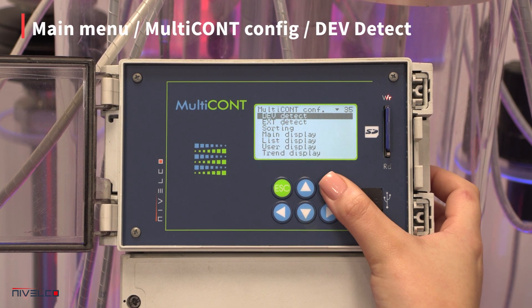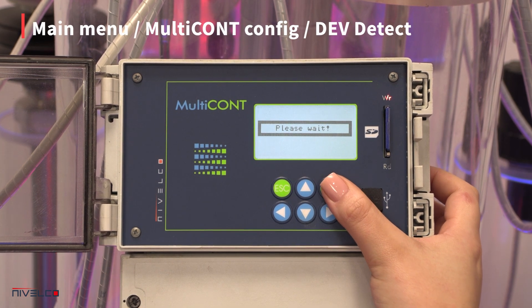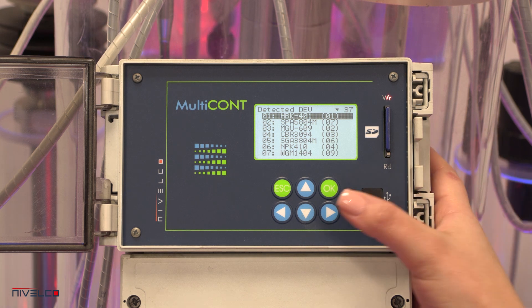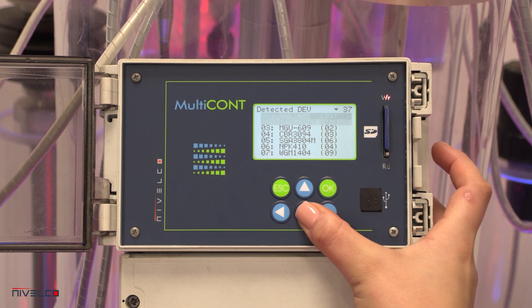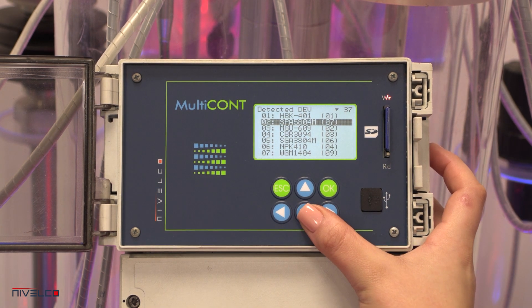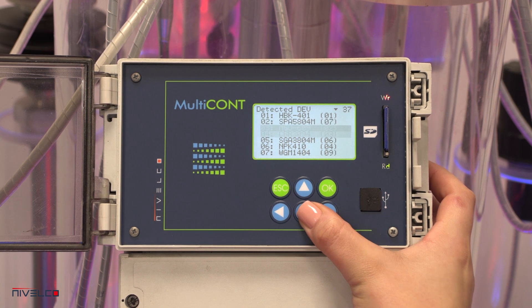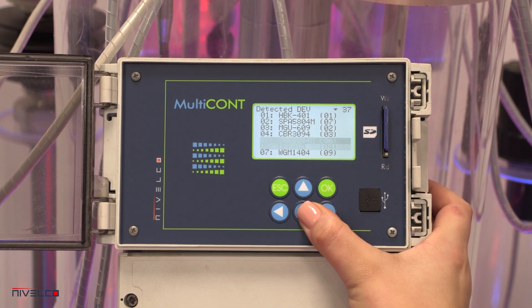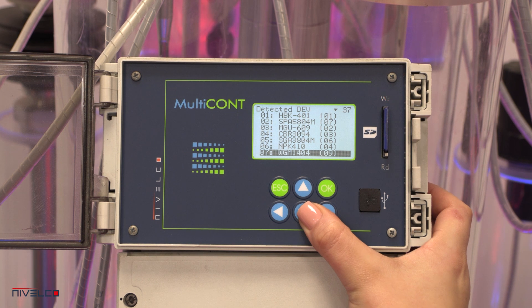The device detect function detects the connected instruments and adds them to the list of devices. If there are two or more devices in the network, a unique short address must be assigned to each transmitter, and the HART addresses may not be zero.